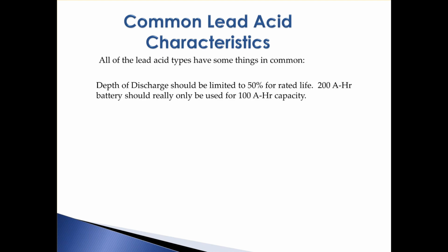First, depth of discharge should be limited to about 50% for rated life. A 200 amp hour battery should really only be used down to about 100 amp hours of capacity. You can use it further, but the more capacity you take out, the more you shorten its life, with the potential, if you run it down to zero, of completely damaging the battery and making it unusable. If you use less than 50%, you'll get longer life, but 50% is the number we're using for discussion purposes.